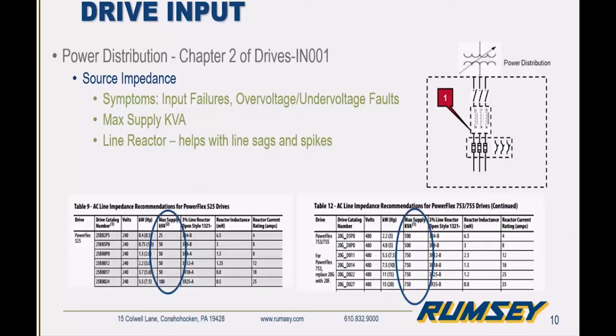We want to make sure, obviously, we determine what the source impedance is. Also, if you have an application already and we're experiencing input failures on drives or overvoltage or undervoltage faults, it could be a good indication that we need to have a reactor out there to prevent and protect, provide some buffering, help with line sags and spikes.